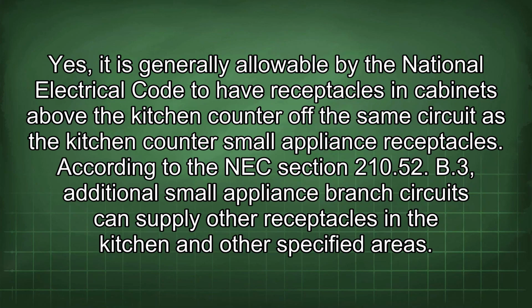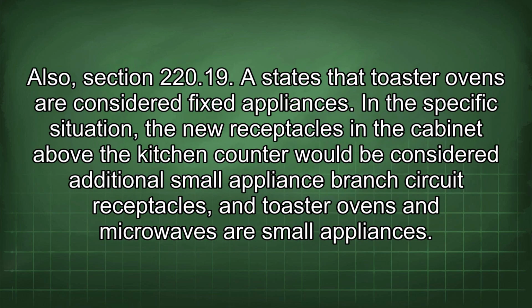Yes, it is generally allowable by the National Electrical Code to have receptacles in cabinets above the kitchen counter off the same circuit as the kitchen counter small appliance receptacles. According to NEC section 210.52(B)(3), additional small appliance branch circuits can supply other receptacles in the kitchen and other specified areas. Also, section 220.19 states that toaster ovens are considered fixed appliances.